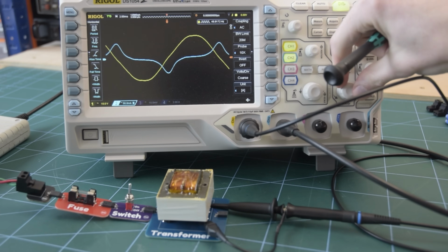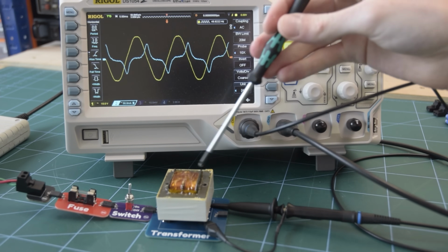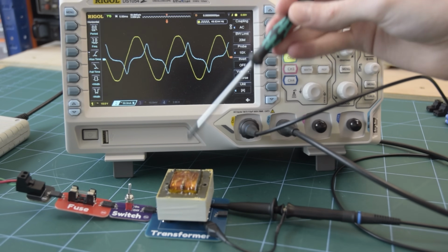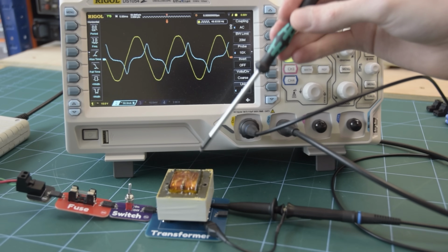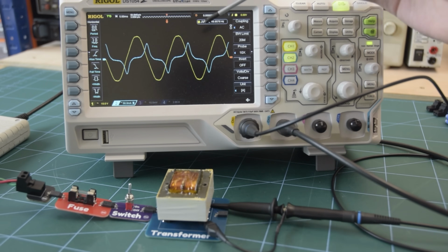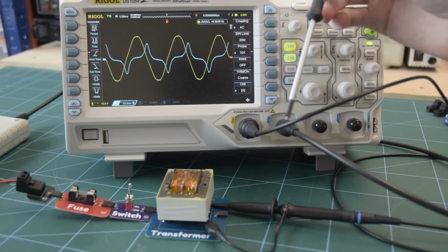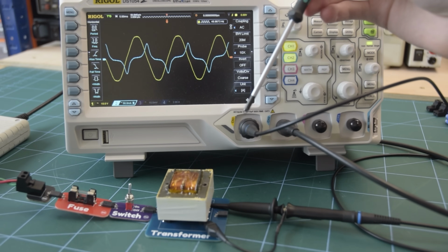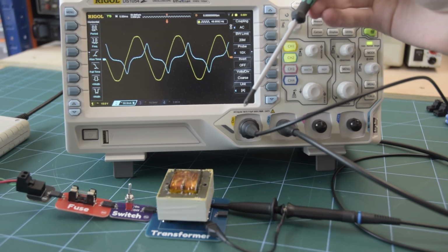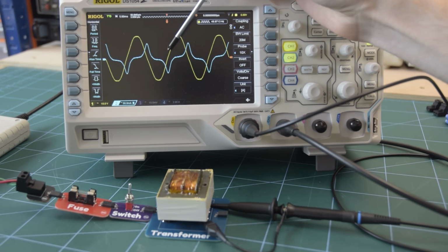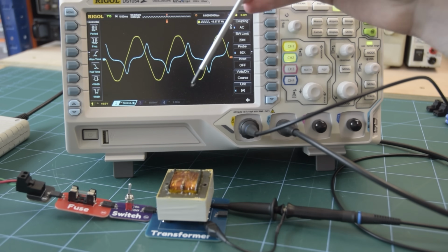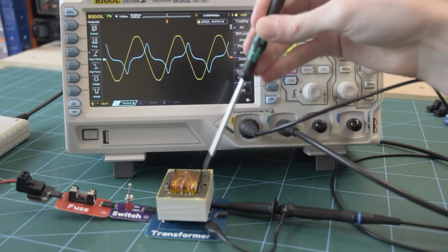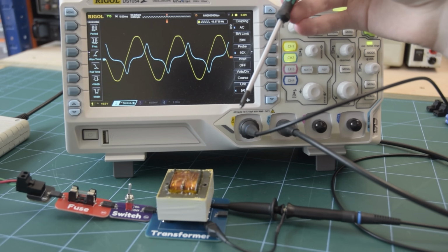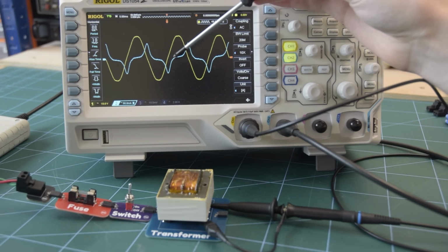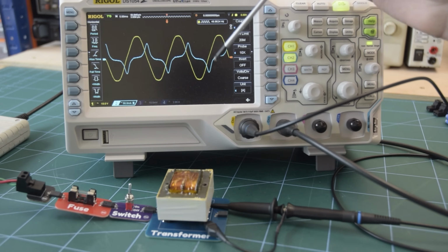It's not unusual to have a little saturation in mains frequency transformers, just to squeeze out as much performance as possible from a certain size. I suspect this is a bit more than this transformer was designed for, because it's rated for 230 volts, and my mains voltage today is 247 volts, meaning the area under this voltage curve is a decent amount more than designed for. So at 230 volts, this blue waveform might be a bit nicer.